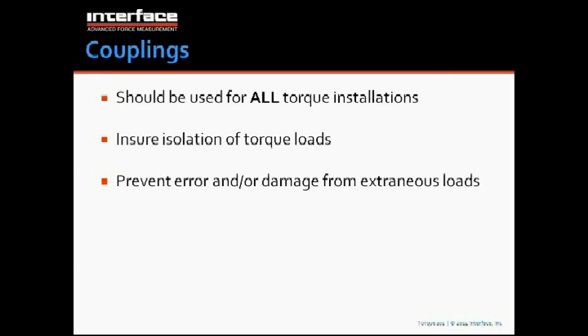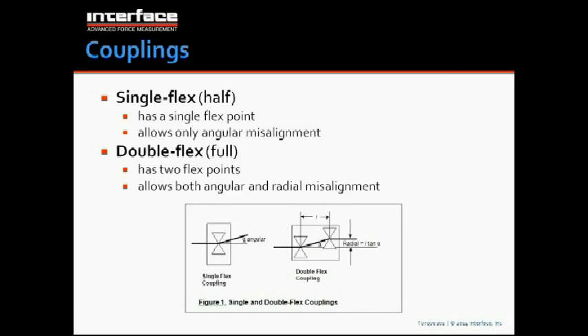They isolate the torque sensor from extraneous loading, bending, and vibration loads; those kinds of things can be isolated using couplings. And also they prevent errors and damage. You can definitely ruin bearings and bend torque sensor shafts and wear them out if you don't use appropriate couplings. Basically, couplings come in single flex and double flex types. Single flex is sometimes called a half coupling, and double flex is sometimes called a full coupling.